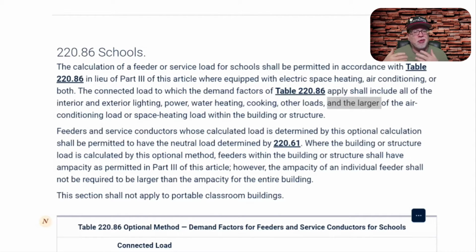They will have general lighting that typically is going to be a continuous load, and they're really not taken into consideration under 220.86. In fact, they could skew the numbers. So you're not allowed to do that. So the easiest way for you to remember that is portable buildings calculate separately, and then ultimately you'll add that value to your overall if they're fed from the main school, for example. But you're not going to add them into the lump. Okay, so just keep that in mind.